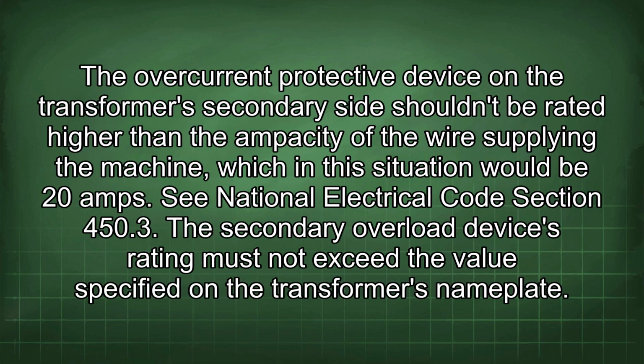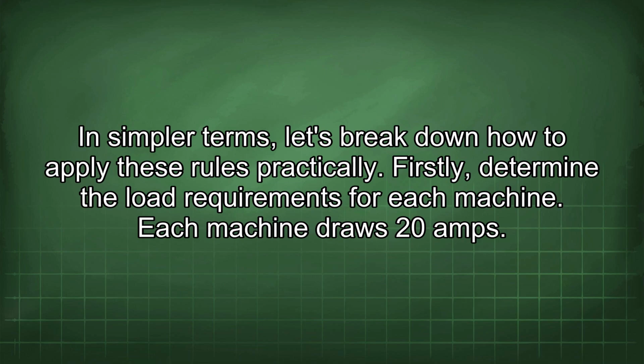The overcurrent protective device on the transformer secondary side shouldn't be rated higher than the ampacity of the wire supplying the machine, which in this situation would be 20 amps. See National Electrical Code Section 450.3. The secondary overload device's rating must not exceed the value specified on the transformer's nameplate. In simpler terms, let's break down how to apply these rules practically.